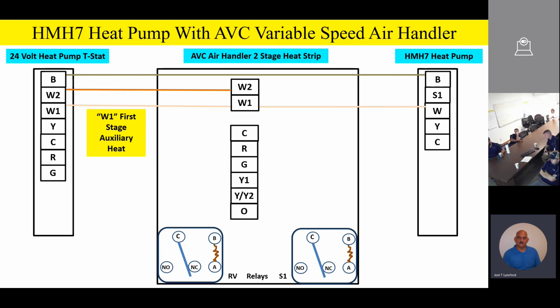It's a comfort thing. A lot of times the complaint you'll have from a homeowner, especially if they're new to heat pumps, is, gee whiz, this thing kind of blows cold air every time it starts. Is it supposed to do that? Well, what the HMH7 engineers did when they designed this is they bring the heat strips on for about a minute to kind of preheat the air every time we go into the heating mode of operation. It's actually designed to do that.